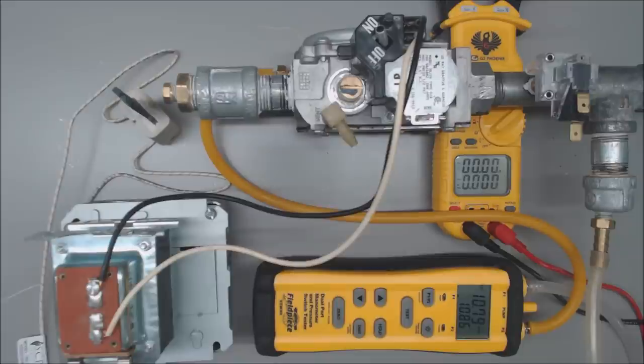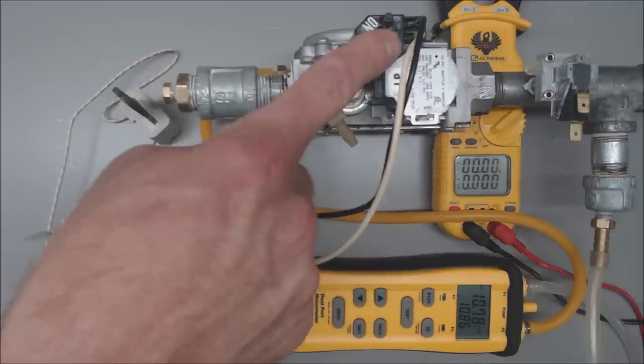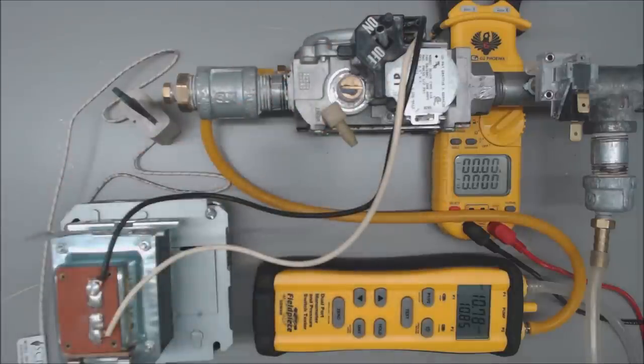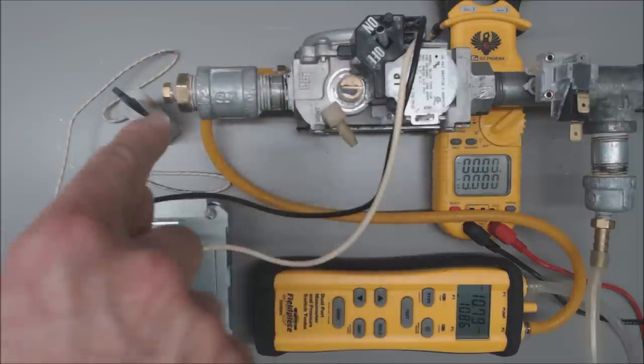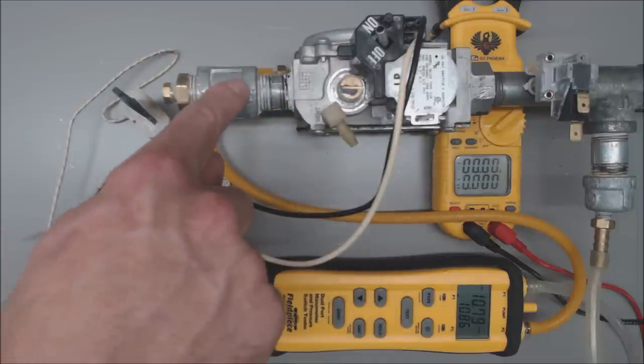So then what you're going to want to do is wait for the sequence of operation to have the hot surface igniter turning cherry red and you want to read voltage over on those two terminals. At the same time, if you do have 24 volts here, you want to make sure that you're checking your outlet gas pressure.